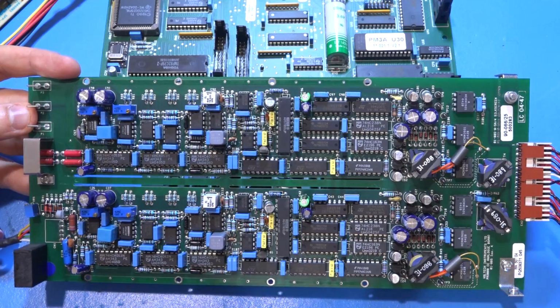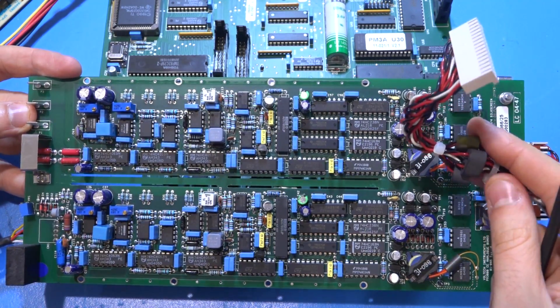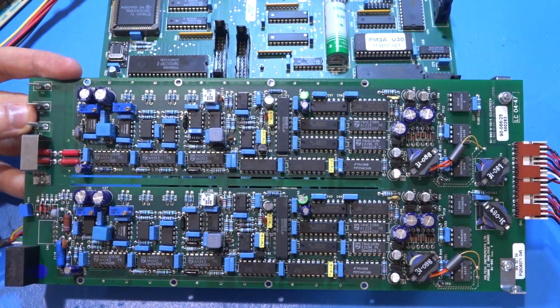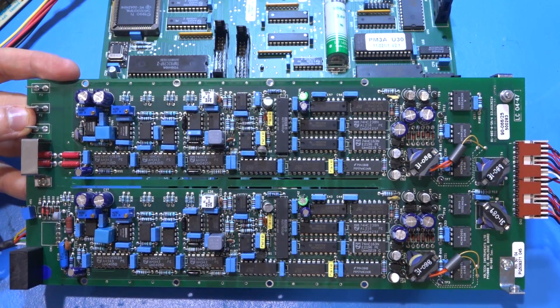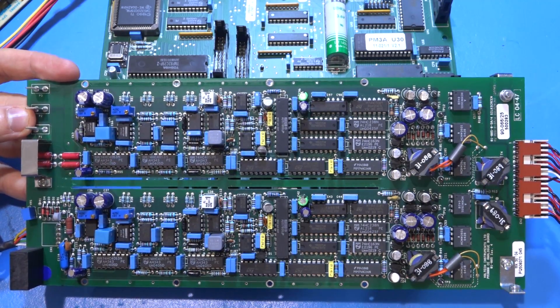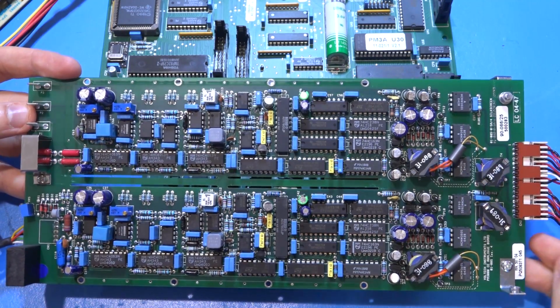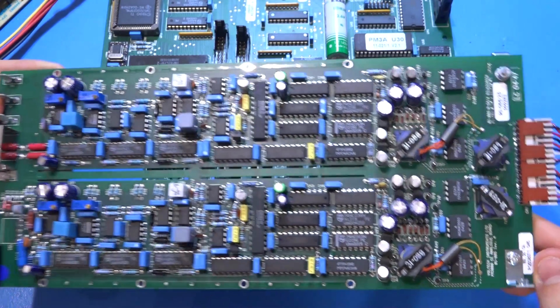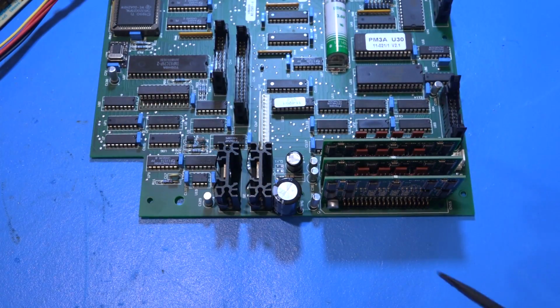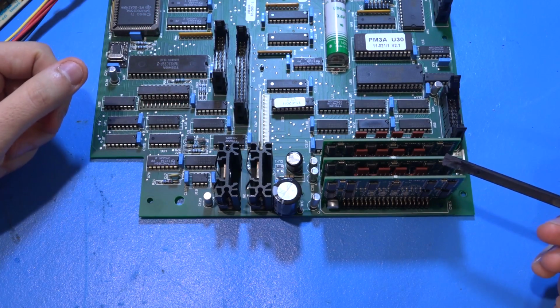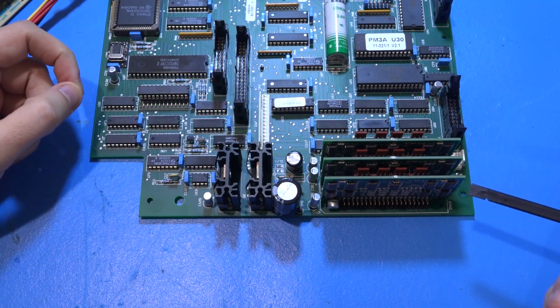So other than that, there is really not much going on. These beads are, of course, because they're twisted pairs they've created for the pulse transformer link as well as the opto-isolator link. So that's all done quite nicely. So we can go ahead and put this back together and see if we can bring it back to life. Unfortunately, that's the only way to test it, because I cannot have the display and everything else connected. The cables are just too short. This is not designed to be serviced.